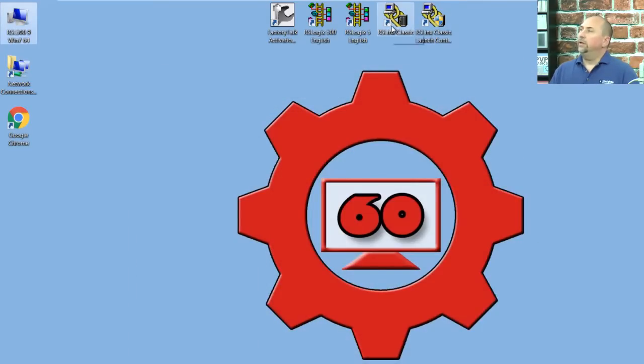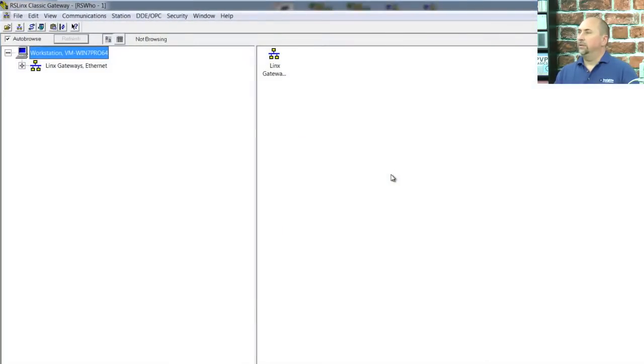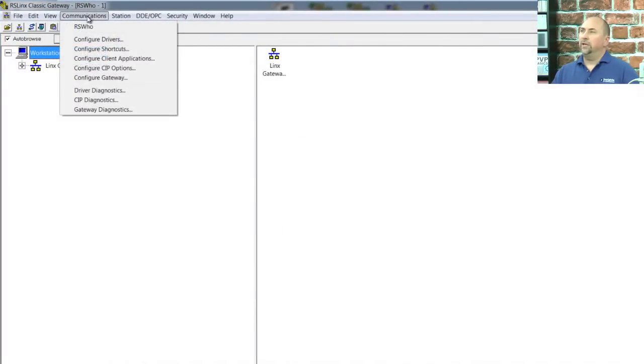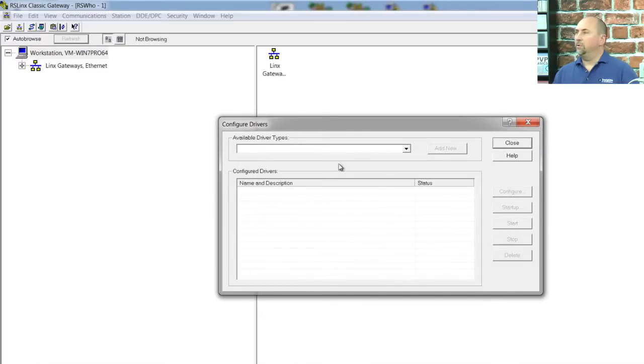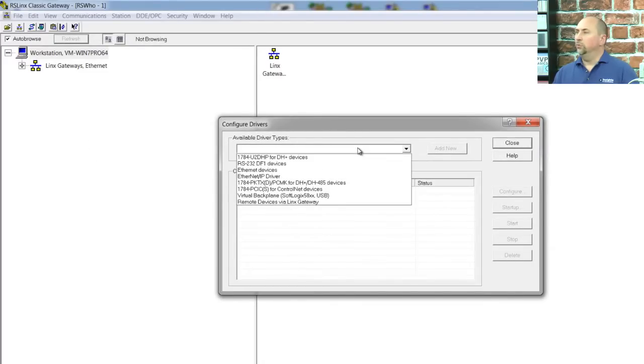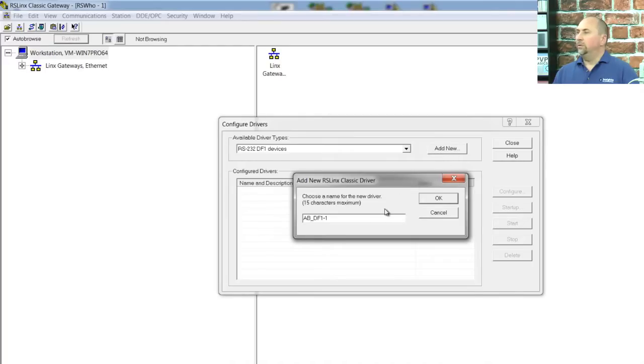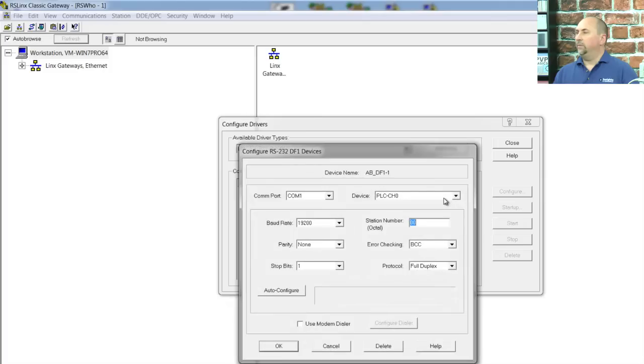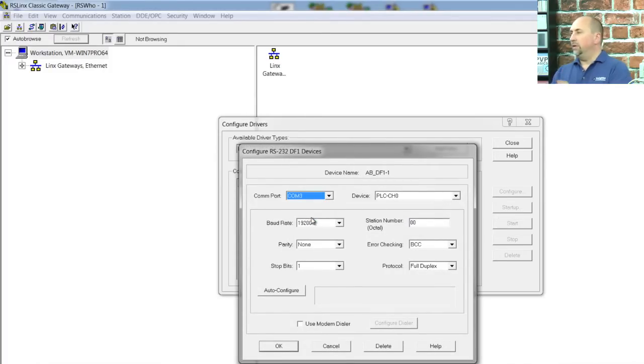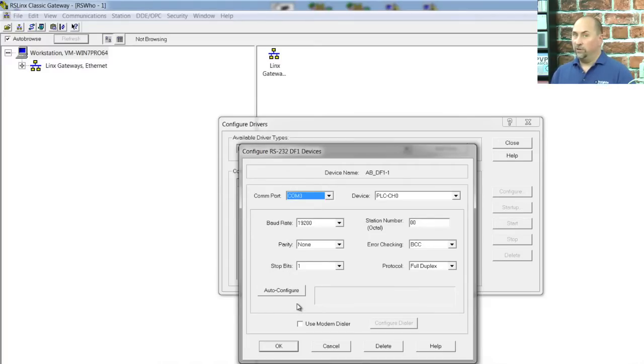Now that I know that, I'm going to go ahead and open up RSLinx Classic, and I'm going to go to Communications, Configure Drivers, and I'm going to choose the RS232-DF1 Devices driver. Click on Add New, select the default name, click OK, and here I will select COM 3. Everything else in this window I'm going to let be set up automatically by using the Auto Configure button.